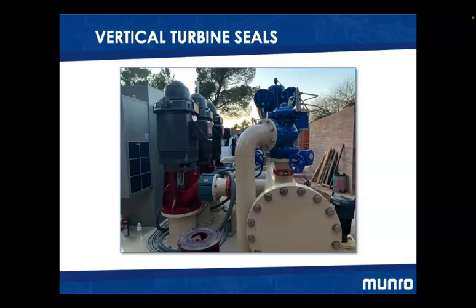Packing style seals typically are going to be a little less money than a mechanical seal, but there is maintenance involved with the packing style seal, where mechanical seals require very little maintenance, short of, if there is a seal failure, then it's all about changing the seal out. Packing style seals have to be maintained, they have to be changed constantly. So you're always pulling the old packing out, putting new packing back in, in order to maintain the operation of the pump in its proper state.